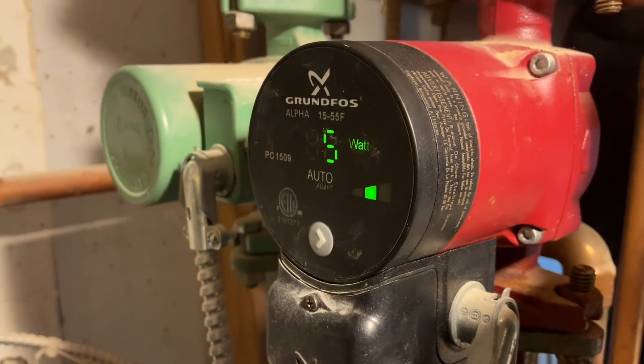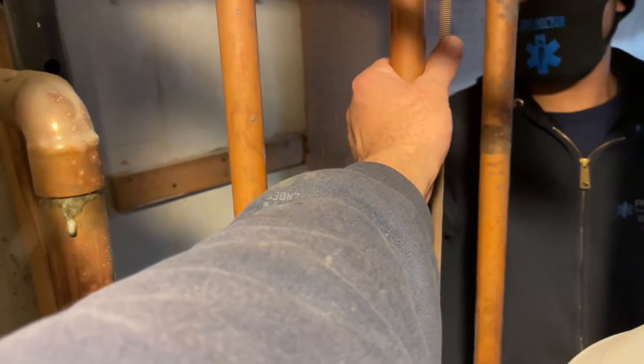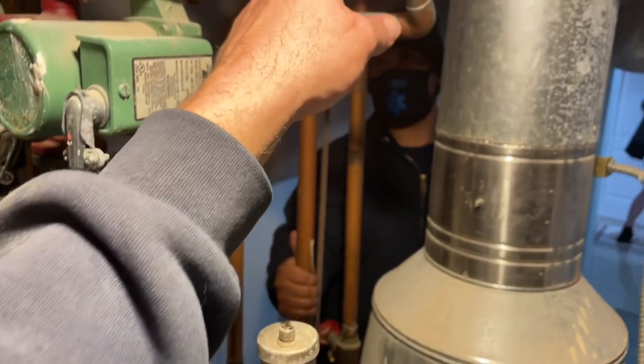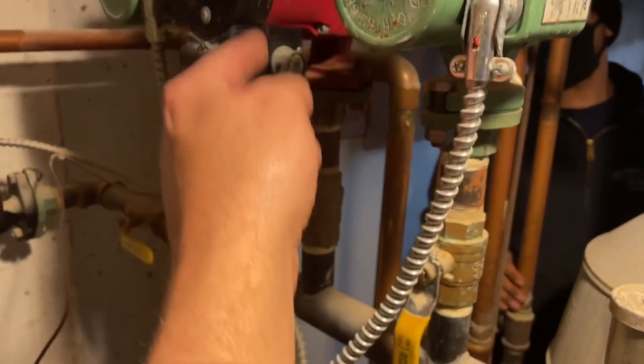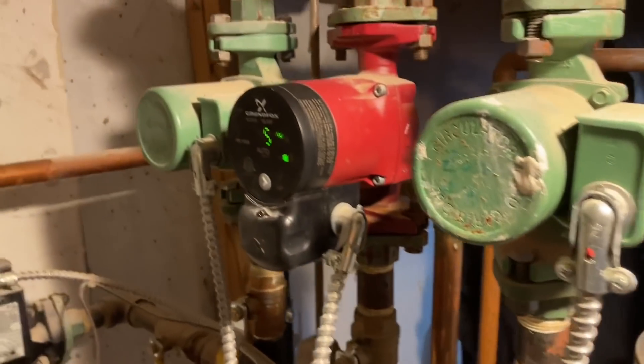Because this pipe is cold — it's not circulating any water. I have zero gallons per minute on the circulator, but my return pipe is hot. So when another zone is on, water is being sucked in from the return, all the way through that zone, back through the circulator, through the flow check, and into that zone with the bad circulator.